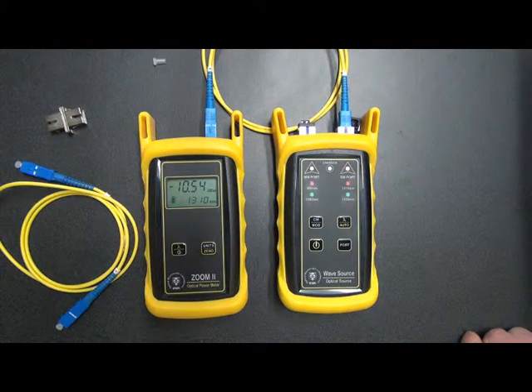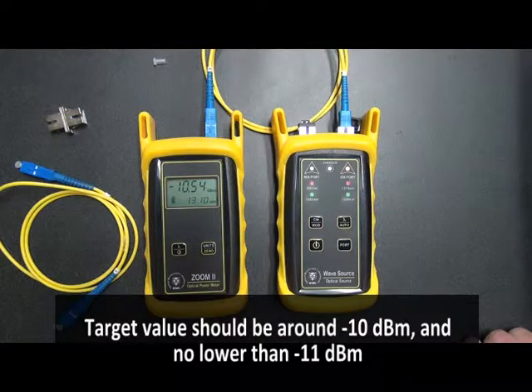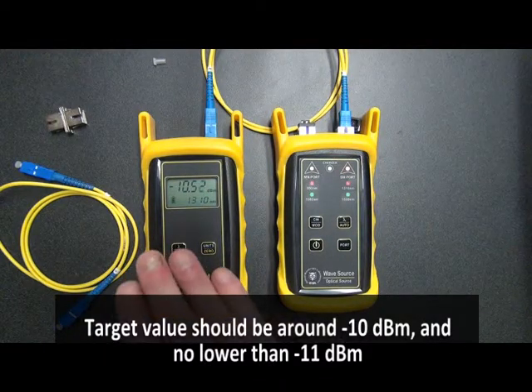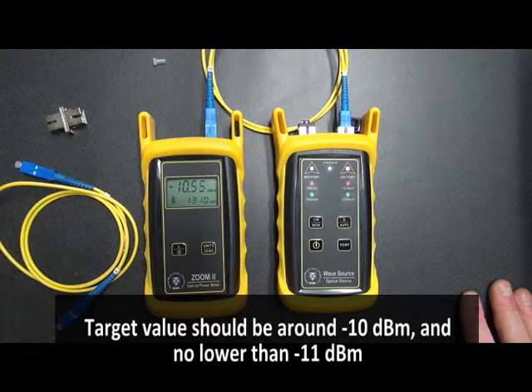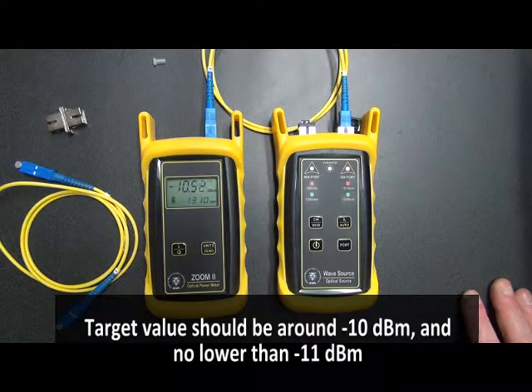Okay, so now what we see is a reading of minus 10.54. Our target value is minus 10 dBm. That's where our single mode sources are calibrated at according to NIST. Now this is okay. The reading could be a little higher, a little lower, but it should be around minus 10. In this case it's a little lower, but it's still acceptable. If we're falling below minus 11 dBm, then there might be something further wrong with the cable and it should be replaced.